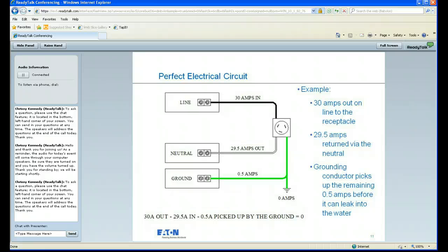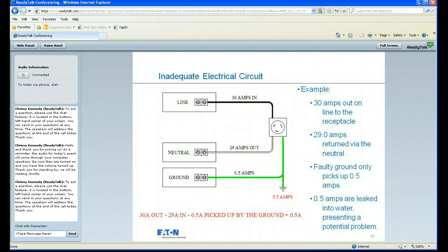In a perfectly healthy or perfectly adequate electrical circuit, again, just as a blown-up example, we're going to have 30 amps of power going out. Our neutral here picks up 29.5 amps, and the ground wire picks up the remaining half of an amp. That means that we're not having any leakage into the water here. That is what a properly working grounding system and electrical system will look like.